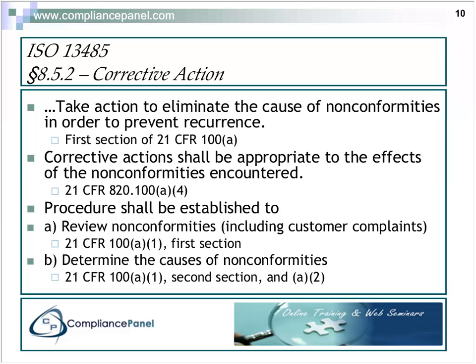Anyway, your corrective action procedure has to review nonconformities, and it specifically says in 13485, including customer complaints, as if that would be something we would avoid. That's 820.100(a)(1), the first section, and you're required to determine the causes of the nonconformities.